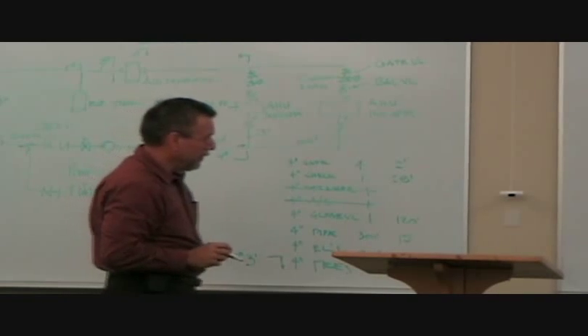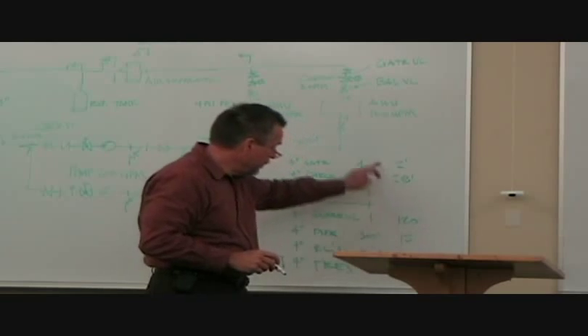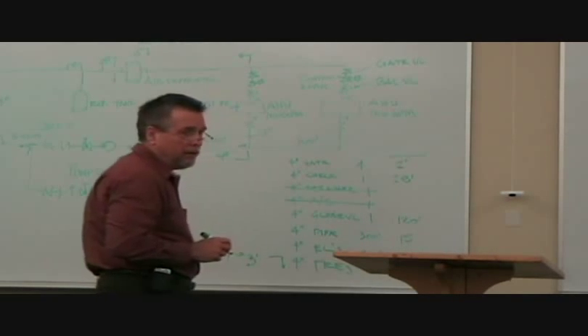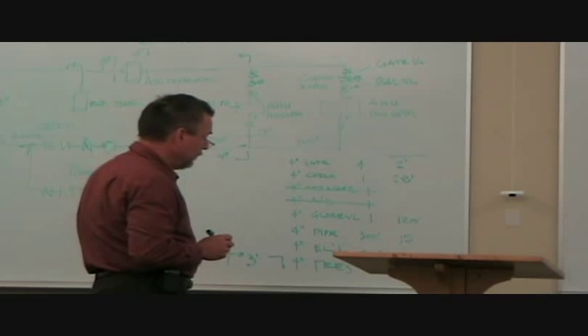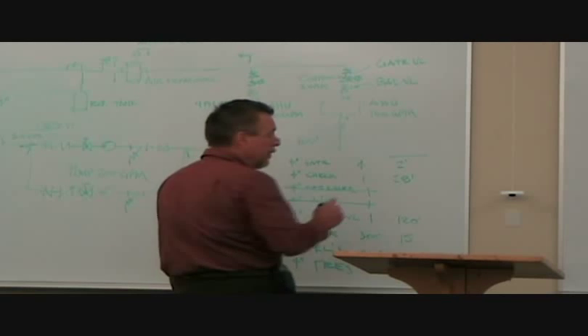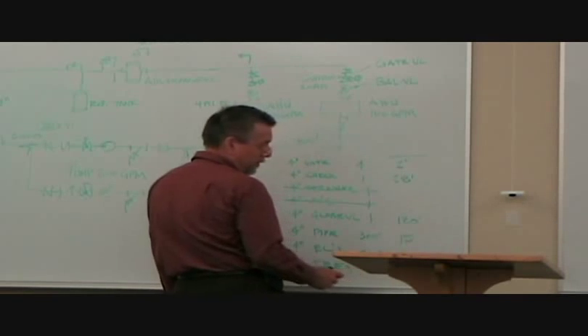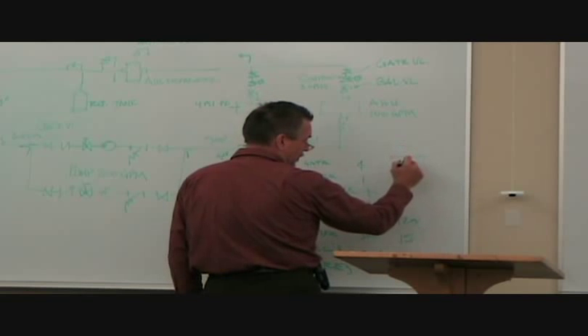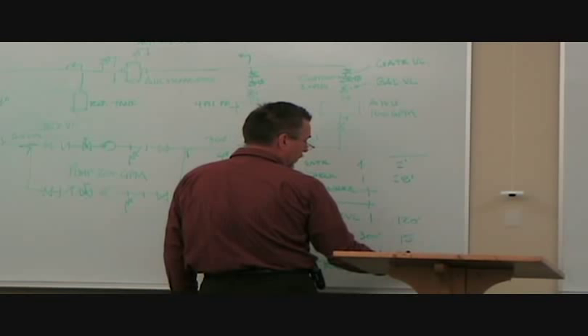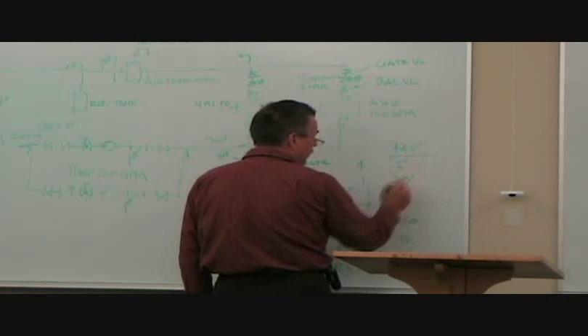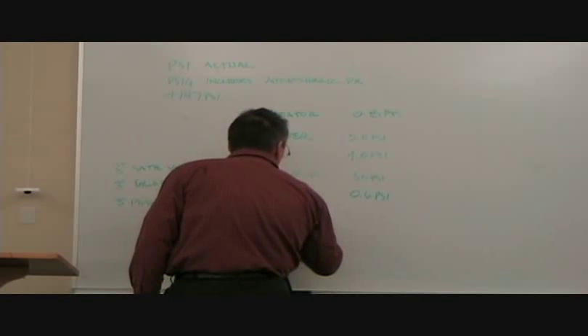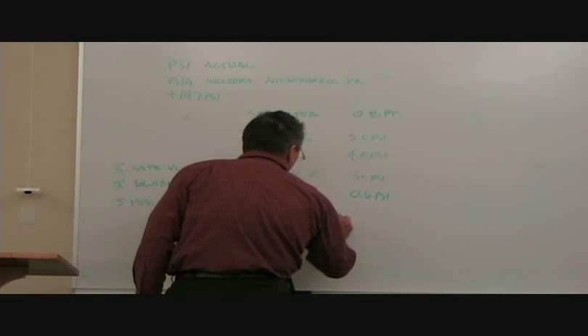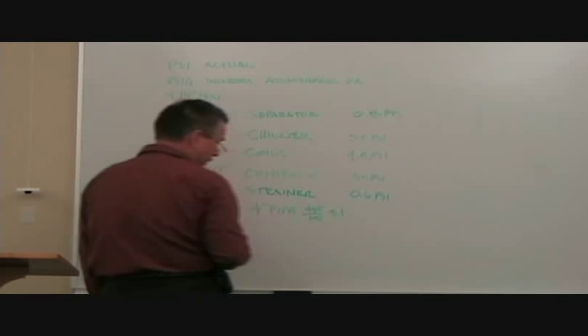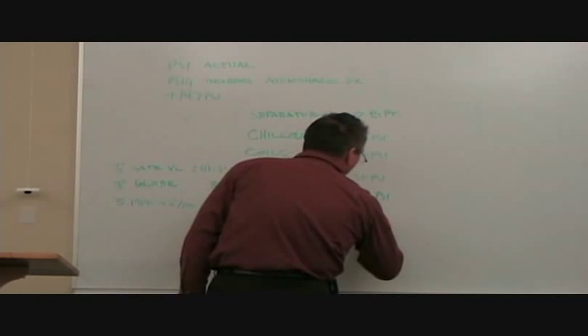Say this is 100 feet. This was 300 feet. Okay, so now I've got all this added up. So what's this add up to, John? Just those numbers right here? 405. Okay. Pretty close. Pretty wrong. Or maybe it's 440. 445. 445 feet. Okay, so I got a total of 445 feet. 4-inch pipe. 445 divided by 100 times 5.1, 22.7. 23 feet of pipe.